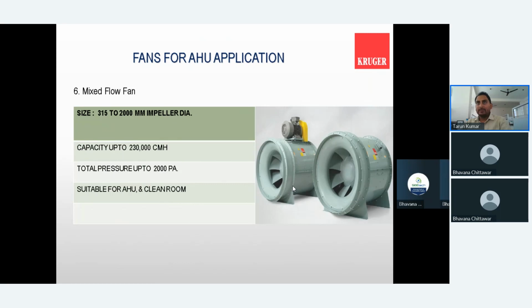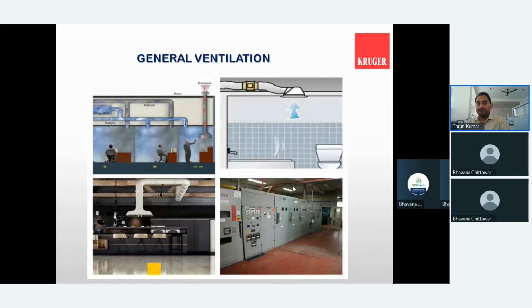So there is a major difference, because as you are aware, in a kitchen exhaust fan your temperature is more than 80 degrees, and very few motor manufacturers make a motor for 80 degree continuous operation. At that point of time, we preferably go with the bifurcation mode, where the motor is bifurcated from the airflow path to safeguard the motor, because the motor is the weakest part of the fan.